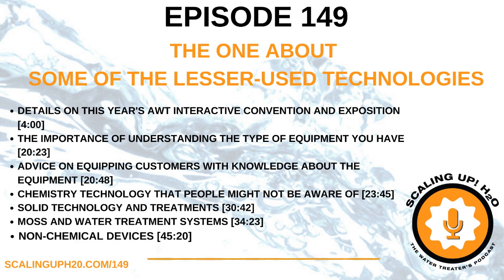When you look at corrosion prevention, because you are actually covering the surface, you've got that ion that's biting into the metal and it's protecting the metal. Corrosion can occur, but it doesn't create a surface where minerals can stick to it. So it actually does a great job of both corrosion prevention as well as scale prevention of the equipment.